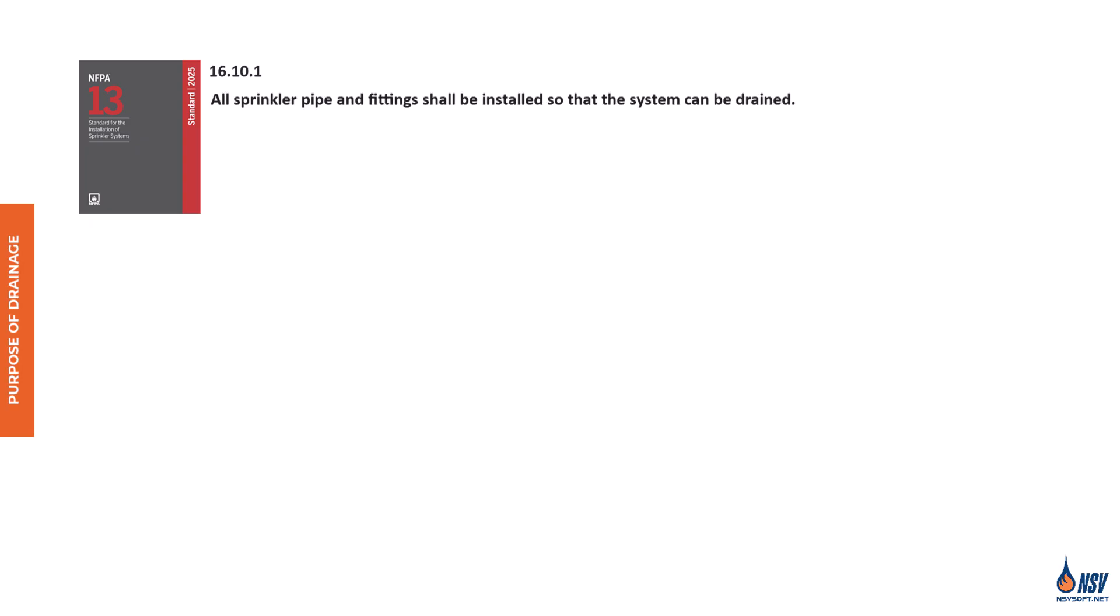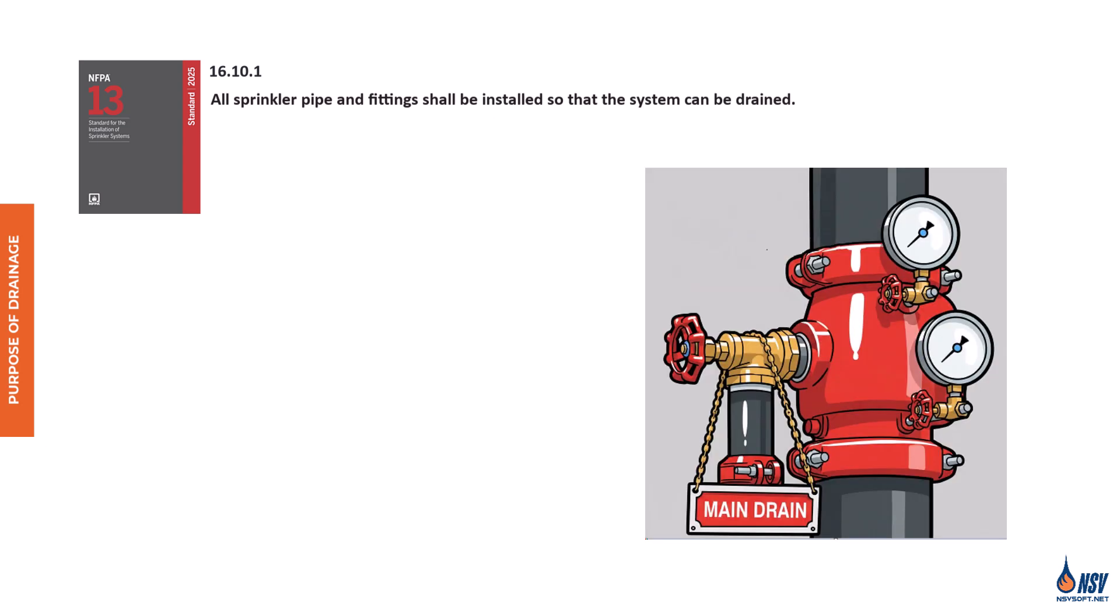According to Section 16.10.1 of NFPA 13, 2025 edition, all sprinkler pipes and fittings must be installed so that the system can be properly drained. Wherever practicable, piping should be arranged to flow toward the main drain valve. Ideally, the entire system should be designed so that all water can be discharged through the main drain. If that's not possible, auxiliary and sectional drainage must be sized and positioned based on the system type and the volume of trapped piping.